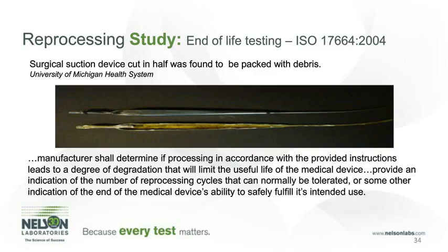Another item that I want to touch on is end-of-life testing. We need to know when a device is unacceptable for use. FDA asks many manufacturers for this information. This is mainly performed by a certain number of steps, which depends on the device itself. So this may include simulating the surgical procedure, performing manual, automated cleaning, disinfection steps, and sterilization steps. The number of cycles depends on the device itself and how long it'll be before the device goes into the end of its use life. As it is very difficult for a healthcare facility to specify how many times a device has been utilized and reprocessed, the device manufacturer normally writes down a lot of the information on how to determine when the device is at its end of use life.